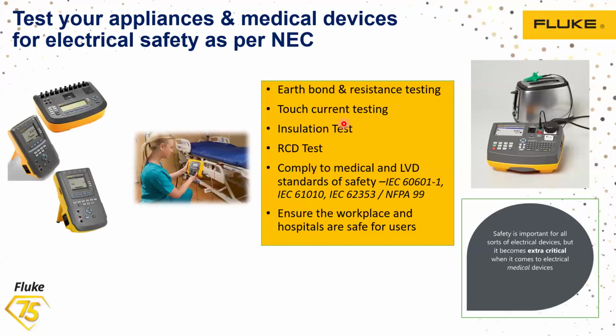Even if somebody is from the medical field, like from hospitals, you definitely have to ensure that even the medical equipment is well within safety. Many equipments will be operating on single phase, right? And some of the equipments will have a metal body. So if the grounding is not proper, what can happen? The leakage current can easily pass through.